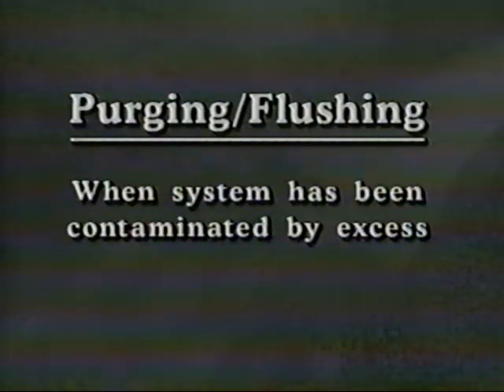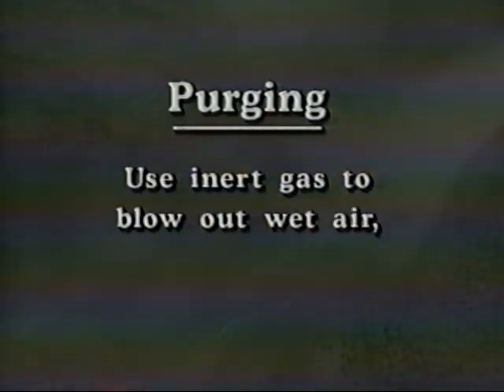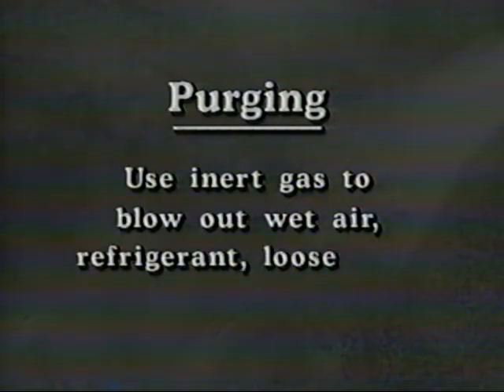Some gauge readings, examples of which we'll see in a moment, may indicate the necessity of purging or flushing the system. The system must be purged or flushed when it has been contaminated by excess water, oil, or dirt. Purging involves the use of a dry, inert gas, such as nitrogen, to blow out wet air, rust, or loose dirt from the plumbing. Do not use shop air.